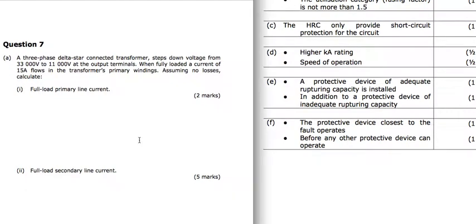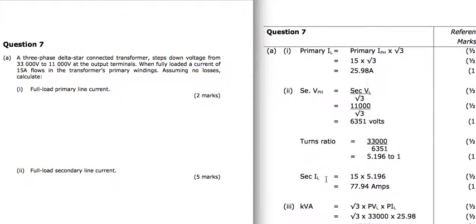Question 7, we're going to do a transformer calculation. Three-phase delta star steps down from 33 kV to 11 kV at the output terminals. When fully loaded, a current of 15 amps flows in the primary windings, assuming no losses. So we're going to calculate the full load primary line current. Now we're told the phase primary current, because we've got 15 amps flowing in the windings, so that's our phase current. Our line current is going to be √3 bigger than that phase current because we're connected in delta. So our line current is 15, which is our phase current, times √3, gives us just under 26 amps.